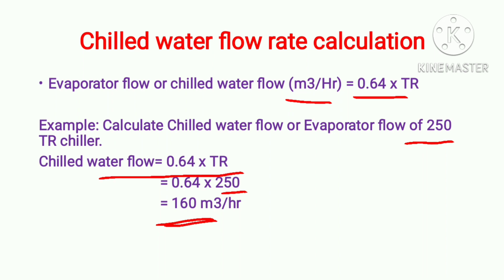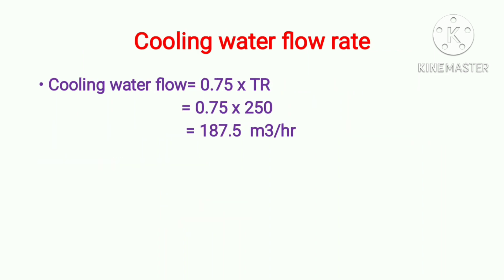Now we will see how to calculate cooling water flow rate, that is condenser water flow rate. The thumb rule for condenser water flow rate is 0.75 into TR. Here our chiller capacity is 250 TR, so we put this value in the formula. After calculation we are getting 187.5 meter cube per hour. This is the shortcut method or thumb rule for calculation of cooling water flow rate.